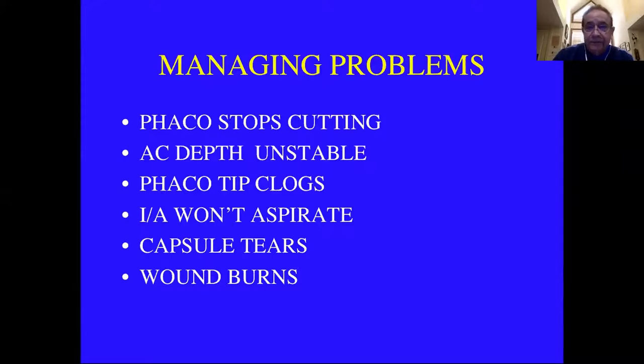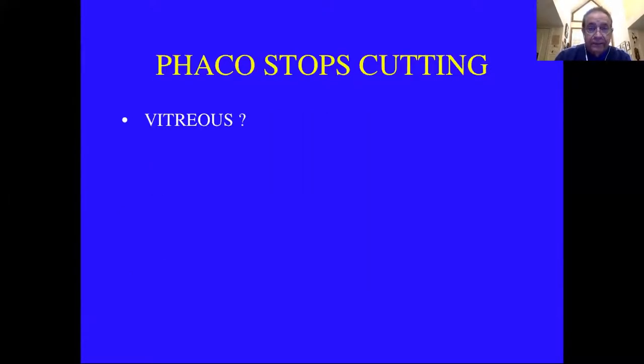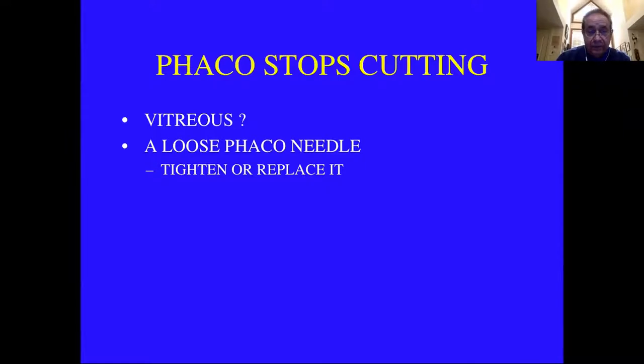You're going to have problems sometimes. Phaco may stop cutting, the anterior chamber depth may be unstable, the tip may clog, you may not get aspiration in IA, you may get a capsule tear, and you can get wound burns. If the phaco stops cutting, first check for a capsule tear and vitreous clogging the tip — phaco will cut lens material or iris or capsule, but it will not cut vitreous. You can wiggle the handle a little and see the end of the needle move loosely if that's the issue. You have to come out of the eye and tighten or replace the tip.